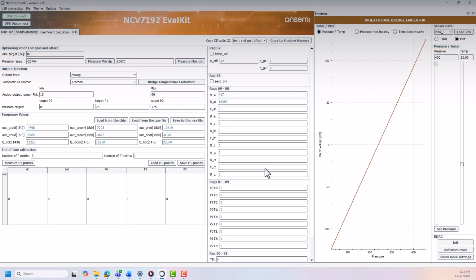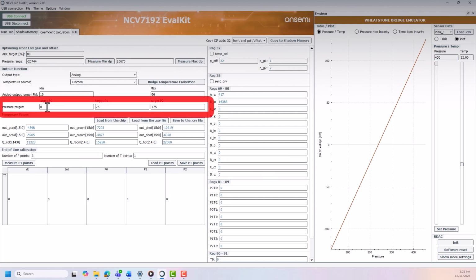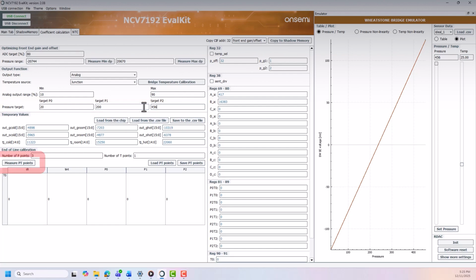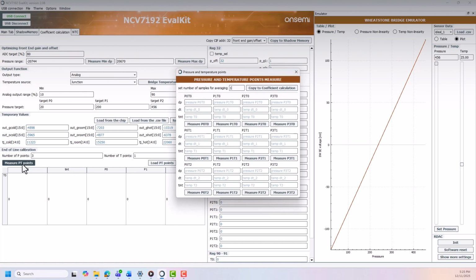In this field, we need to pre-fill target calibration pressures. In our case, P0 is 20. P1 we can select, for example, 200, and P2 is 456. Now click on Measure PT Points button. New window will appear. Because we will strobe just 3 points, we will use just these 3 buttons for P0T0, P1T0, and P2T0. Let's set on the emulator pressure value 20, strobe P0T0 point. Now set emulator pressure 200 and strobe P1T0 point. Now set emulator pressure 456 and strobe P2T0 point.